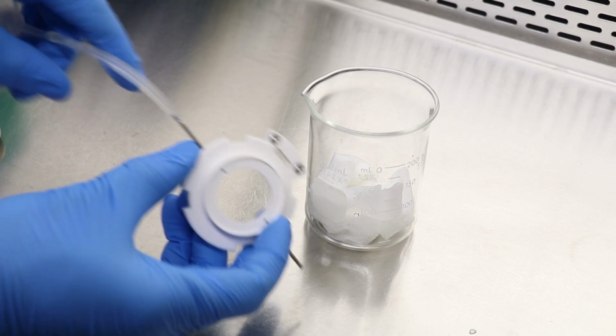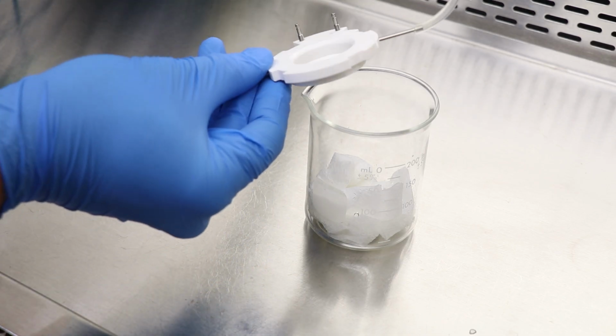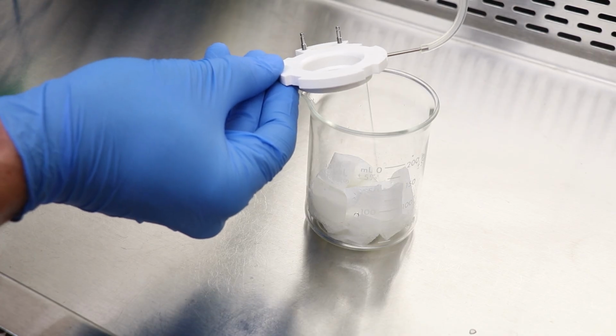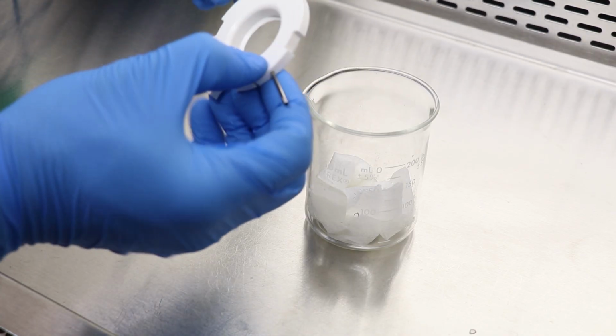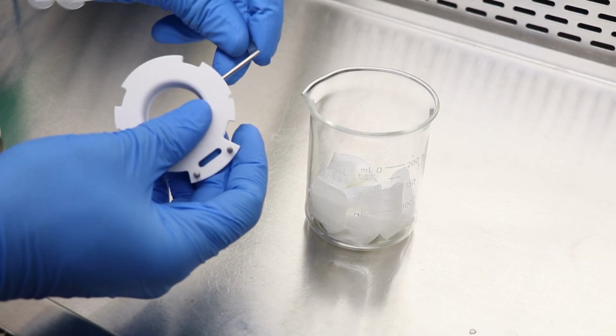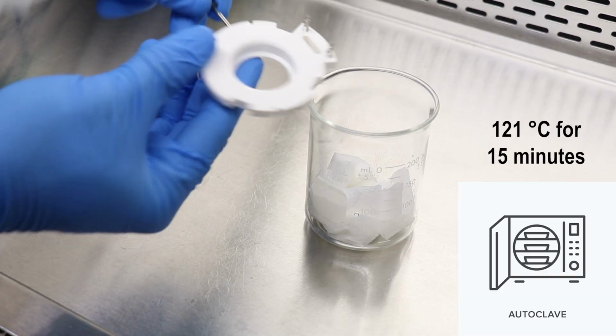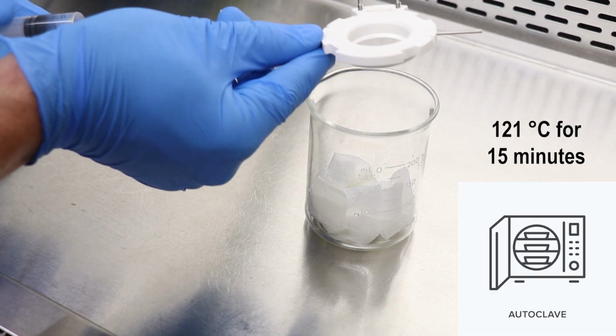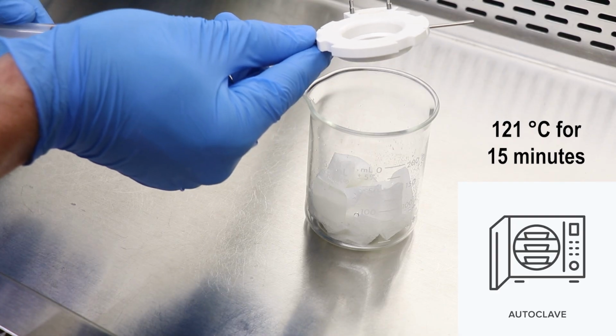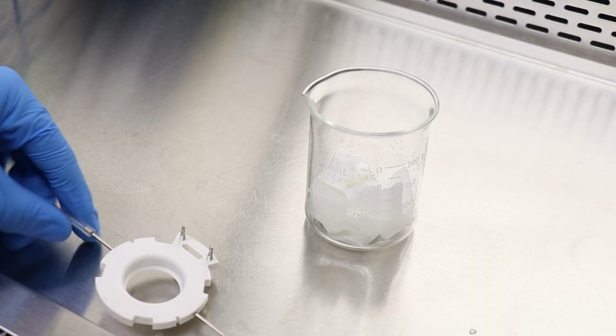Now perfuse the port which was clogged using a syringe with deionized or distilled water and test the flow. If the flow is now normal, then you are ready to finish sterilizing the top by a short cycle autoclave at 121 C for 15 minutes. The top can then be returned to service.